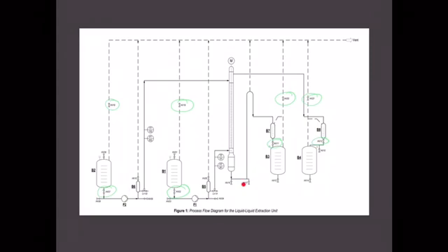Once liquid starts to overflow at the top of the column, stop pump 1 and switch on the stirrer at the control panel. The equipment is now ready for the experiment. For general shutdown procedures, switch off pump 1 and pump 2, then switch off the stirrer at the control panel. Open valves HV12, HV14, and HV16.